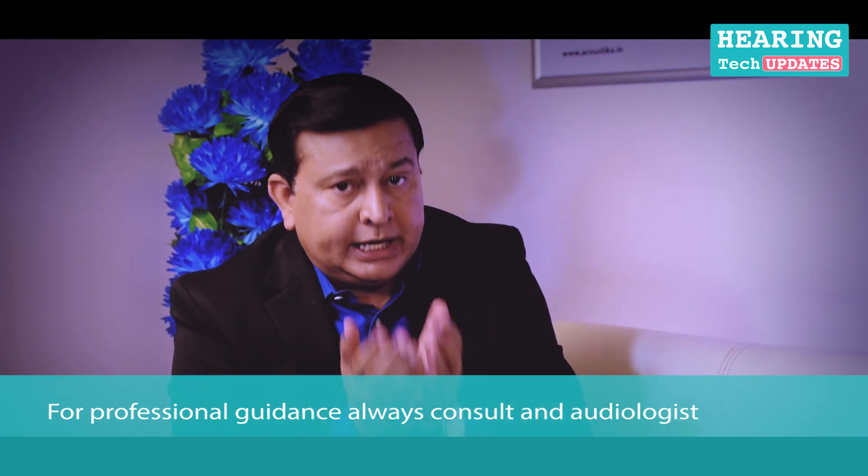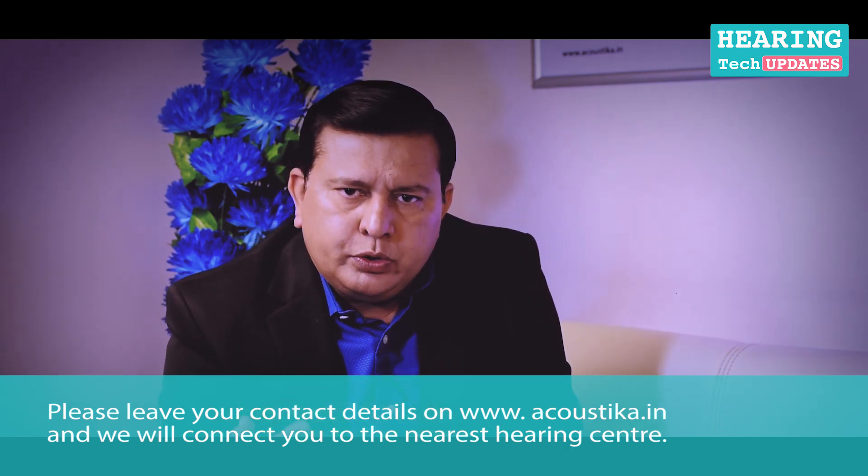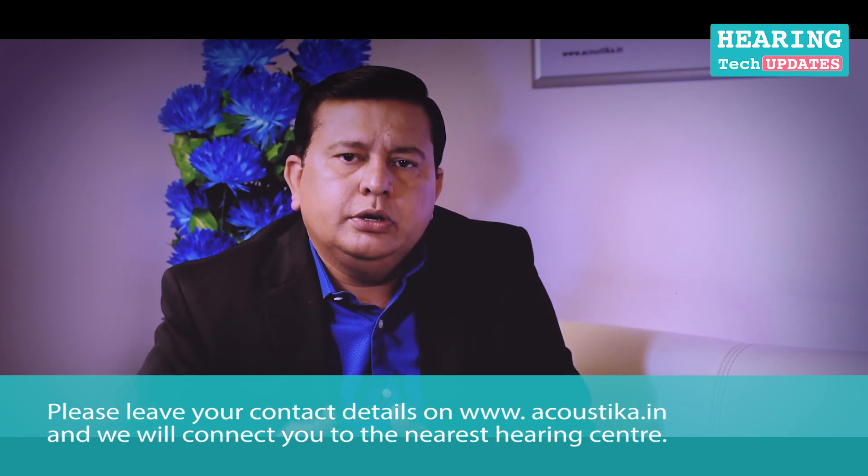To explain to the audience: if today you have 50% hearing loss and start using a RIC, and tomorrow your hearing loss increases by 10 decibels, the same hearing instrument can be used with a higher-power receiver — just by changing the receiver. That is why RICs became popular. Also, in certain cases a completely-in-the-ear instrument couldn't be fitted, and behind-the-ear instruments were too big for people who are active, attend offices, meetings, and conferences. Visibility is also a reason, and RIC keeps the ear completely open.